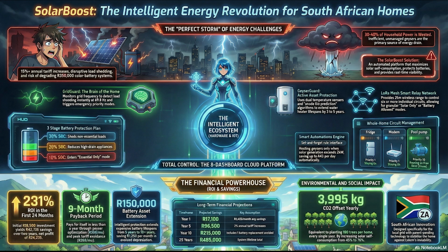Now the system enters stage 2, critical SOC. The triage logic becomes much more aggressive. It looks at the heavy thermal loads. Things generating heat. Right. It immediately forces the geyser relay into a strict solar-only mode, meaning the geyser is mathematically blocked from drawing even a single watt of power from the battery. Wow, okay. It will forcefully disable heavy indoor appliances like the electric oven or tumble dryer. It alters the priority queue for the stove. The system is now actively hoarding the remaining 20% of the battery's chemical energy.